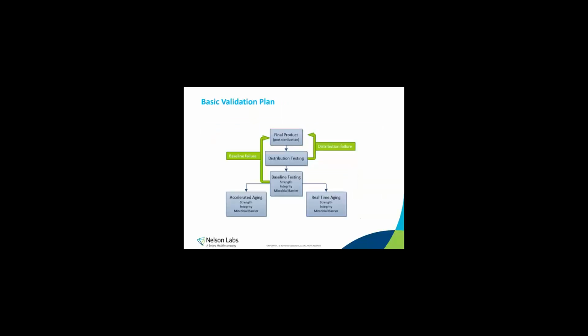Here's the overview of a basic validation plan. You start with the final product in the final packaging and sterilize it using the validated sterilization cycle, preferably a 2x or double sterilization to get to that worst case condition. Then the boxes are run through a distribution simulation, and then the boxes are inspected for damage. If there's a distribution failure, let's say a box crushes in the compression test or splits open in the drop test, then you need to investigate, determine the severity and potential impact. If the severity is low, you may be able to proceed to the next step. But if the severity is unacceptable, then you need to redesign the protective packaging and start over.